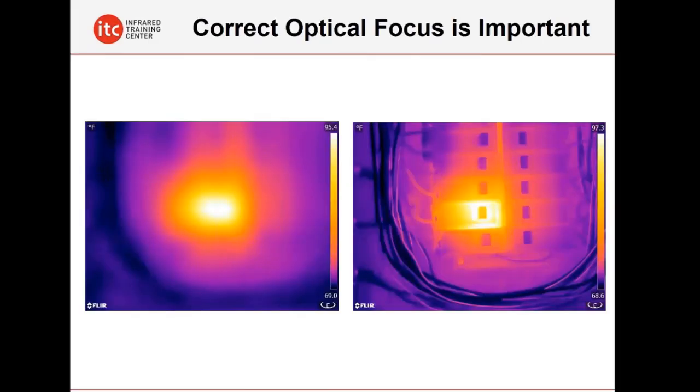You've got to know how to do things like focus. Properly adjusting focus is essential to getting great images with a thermal imager, whether you spent $400 or $50,000. Without proper focus, it's hard to identify what it is we're looking at. You might not realize that improperly focused images also don't reflect temperature values accurately as well. We emphasize a lot of good camera skills in our training classes, like how to properly focus and what you can do to get the best possible focus.